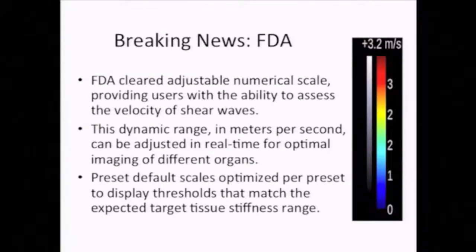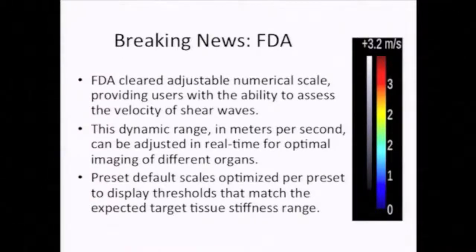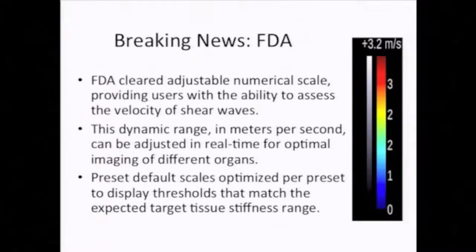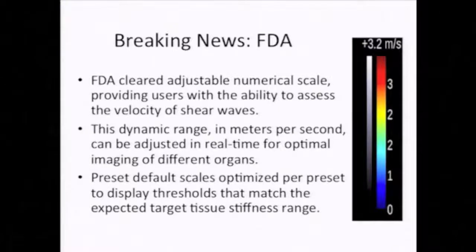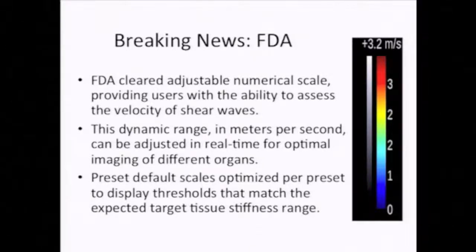There has recently been a change in the FDA approval status of the Explorer. For clinical non-research units in the United States, the color scale now comes preset such that it's optimized for the expected range of velocities per organ. In the liver, it's optimized to show the range between normal liver and cirrhosis, permitting correlation with the adjacent color scale to obtain a visual assessment of the degree of fibrosis.